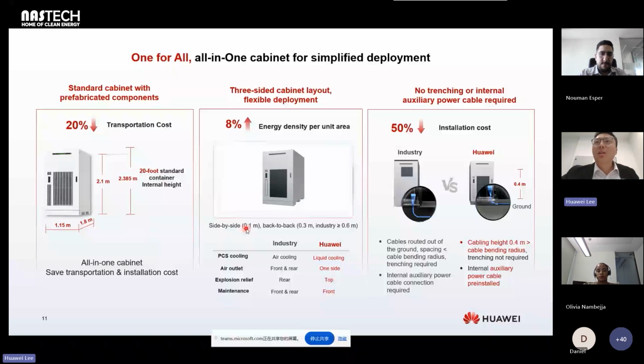Next, no trenching or internal auxiliary power cable is required. In Huawei's design, the cabling height is 0.4 meters, bigger than the cable bend radius, so trenching is not required. For other industry solutions, if the distance doesn't meet the bend radius, trenching is required.